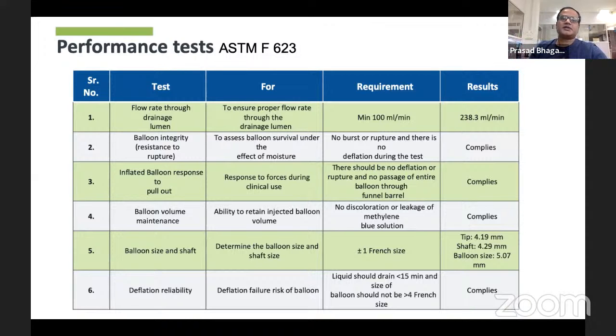But performance testing is the most important, because it gives you an idea whether your device is going to perform perfectly or not. And as I said in my initial slides, we want to bring a quality product to the market. That's why we focused more on the performance test also. Our job would have been done by just showing the biocompatibility studies, but we took one step ahead and did the performance testing also. This testing was done as per the ASTM F623 guideline, which is globally followed to test the performance of the Foley balloon catheter.